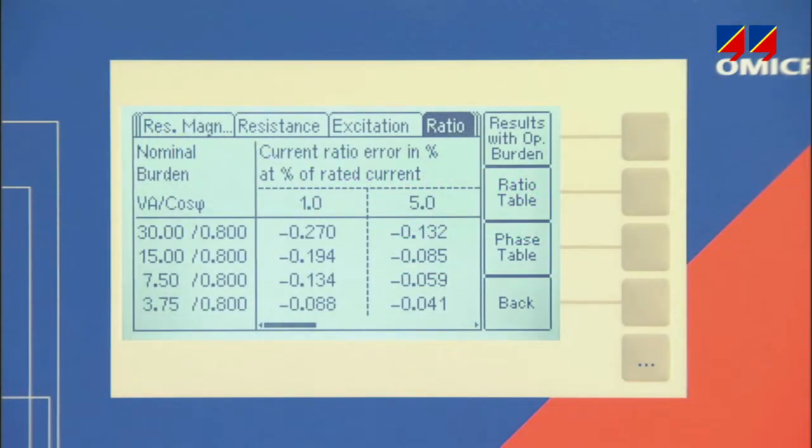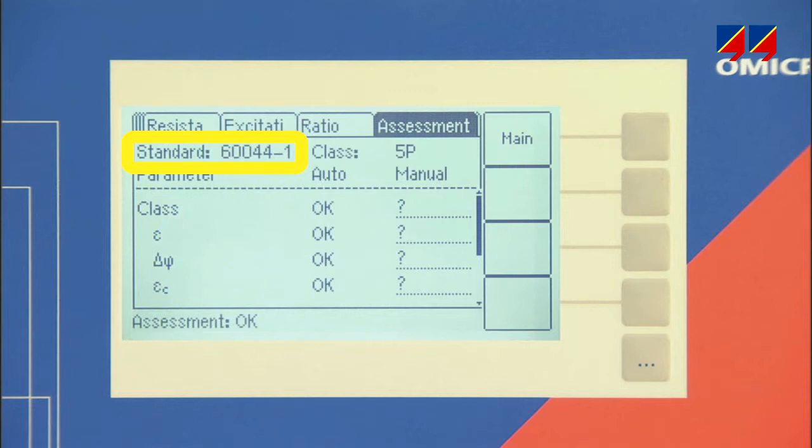For metering CTs, it measures the amplitude and phase angle accuracy for combinations of primary current and burden, as defined in the relevant standard, and automatically assesses if the CT is within the specified limits.